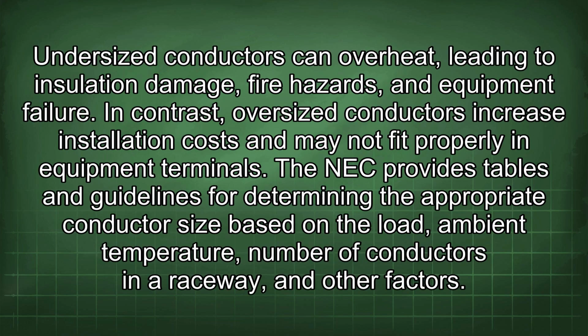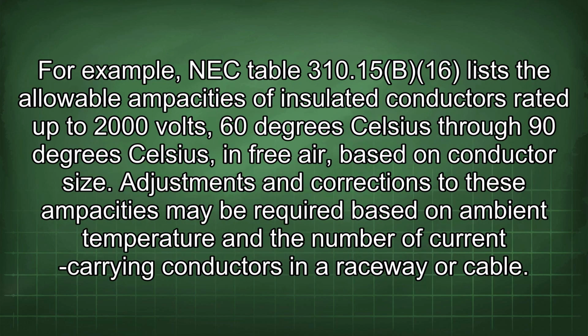Undersized conductors can overheat, leading to insulation damage, fire hazards, and equipment failure. In contrast, oversized conductors increase installation costs and may not fit properly in equipment terminals. The NEC provides tables and guidelines for determining the appropriate conductor size based on the load, ambient temperature, number of conductors in a raceway, and other factors. For example, NEC Table 310.15(B)(16) lists the allowable ampacities of insulated conductors rated up to 2000 volts, 60 degrees Celsius through 90 degrees Celsius, in free air, based on conductor size.